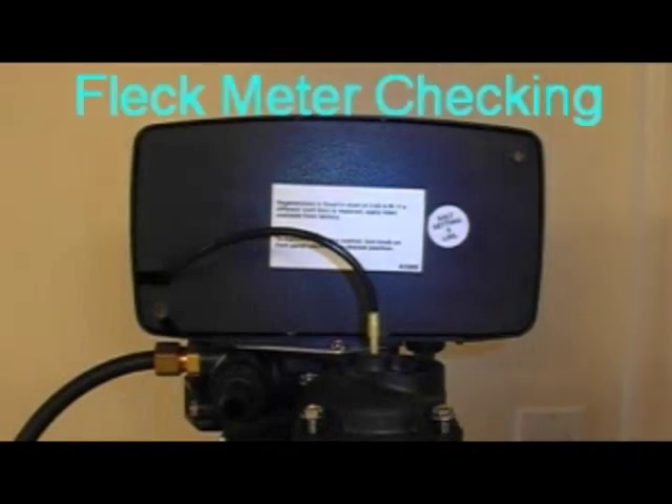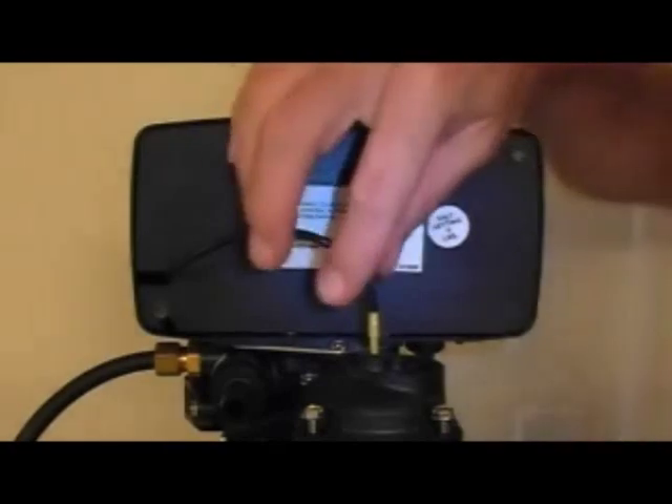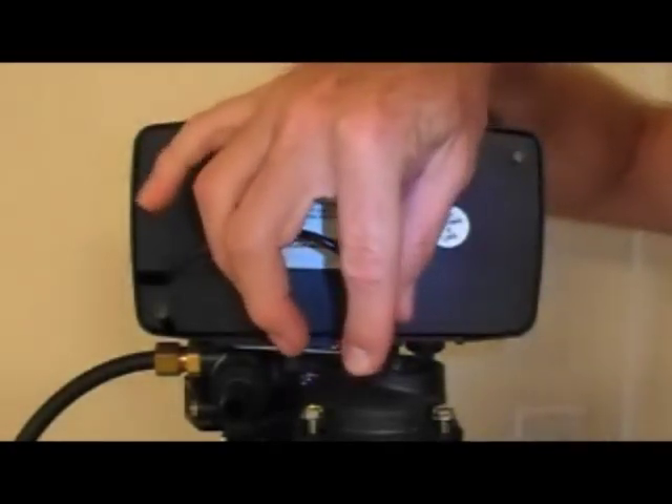If you have the 5600 Econominder, or actually any Fleck Econominder valve, and it does not seem to be counting down the water, you'll want to check this meter dome in the back.